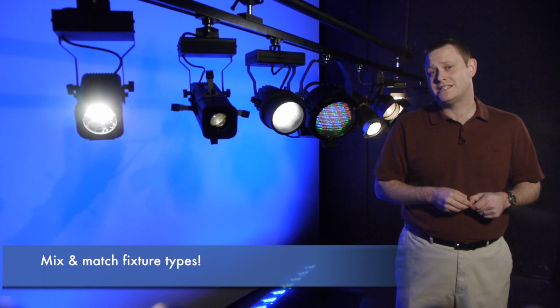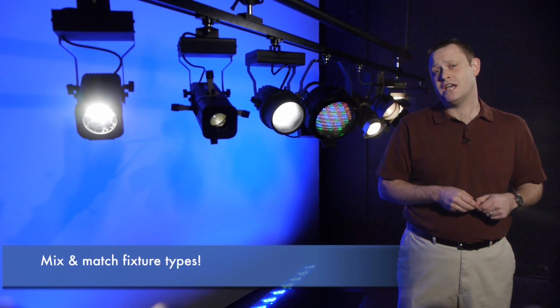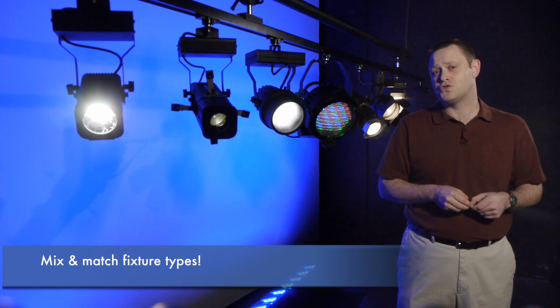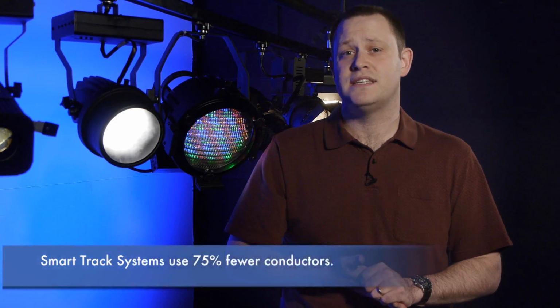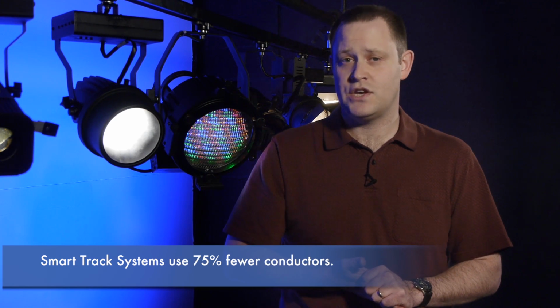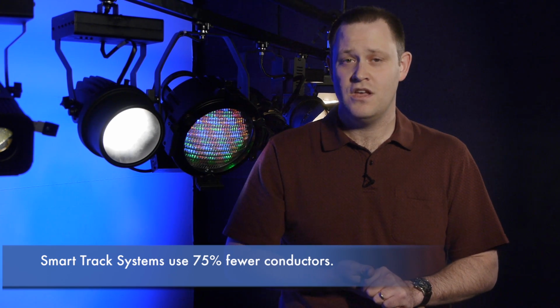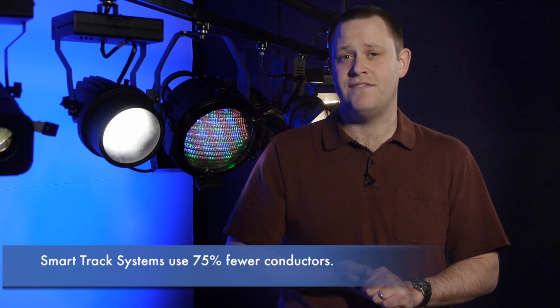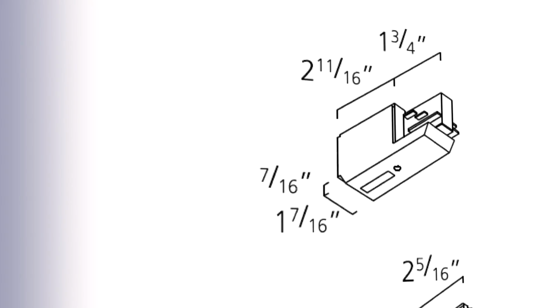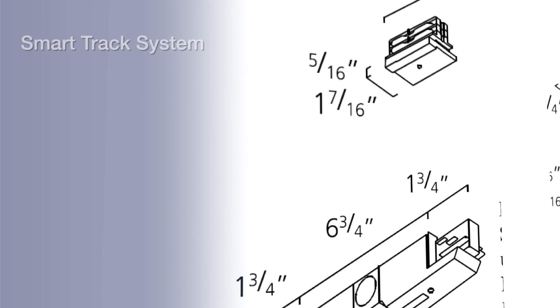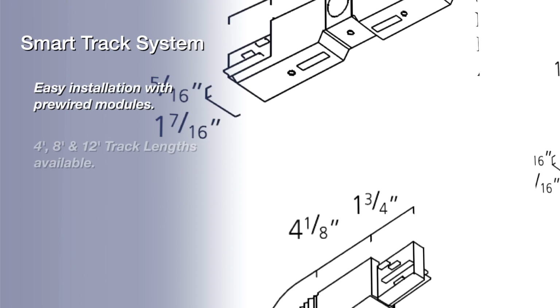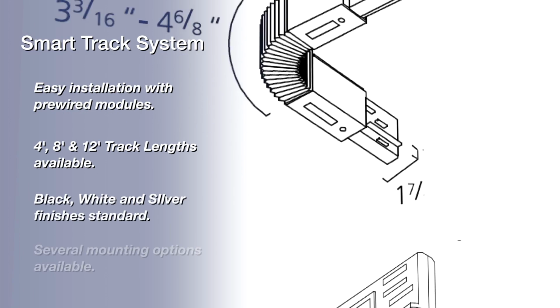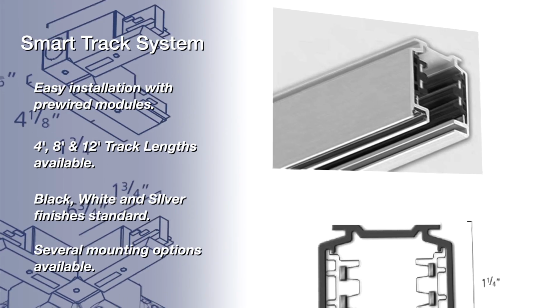SmartTrack fixtures utilize the same power feed regardless of fixture type, while still maintaining individual control of each fixture. Because of the flexibility of design, SmartTrack systems utilize 75% fewer conductors than a traditional dimming system. Fewer conductors means greater cost savings over the installation infrastructure of the overall lighting system. The SmartTrack system can be installed with ease using pre-wired live-end feed modules, straight couplers, L, T, and X connectors to meet the needs of any venue.